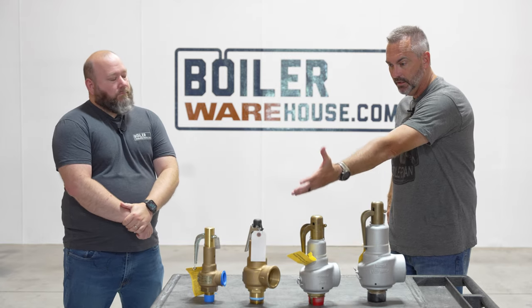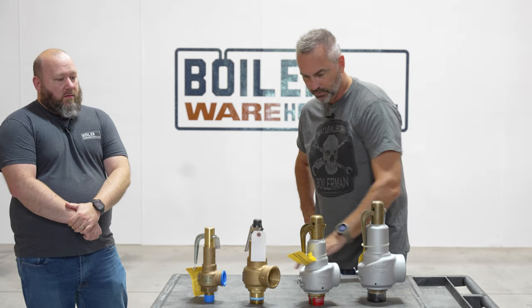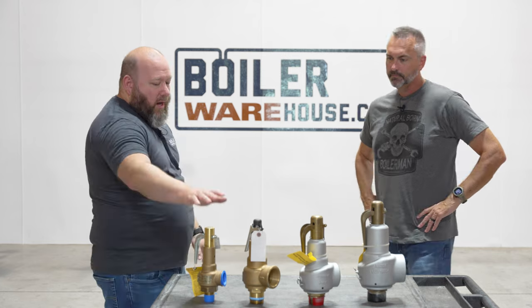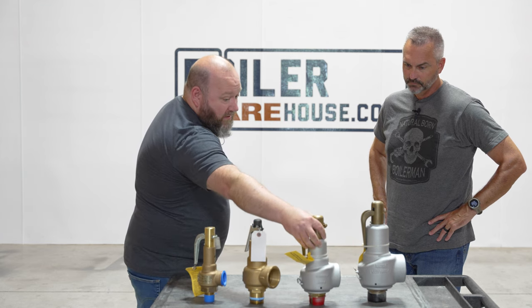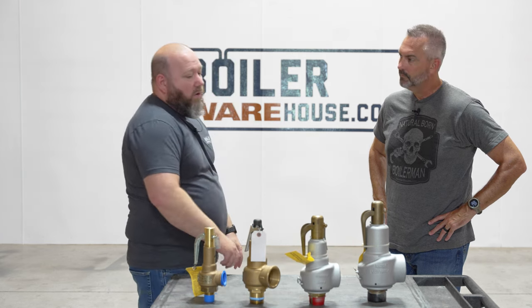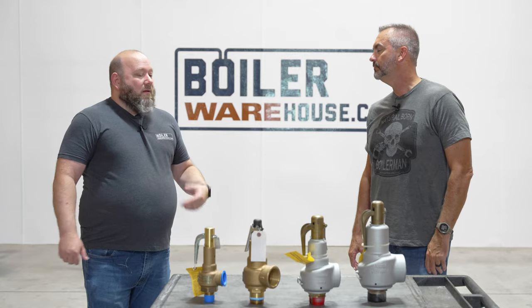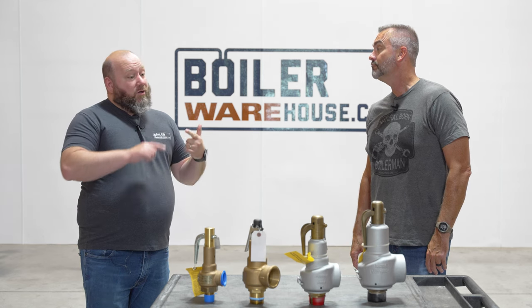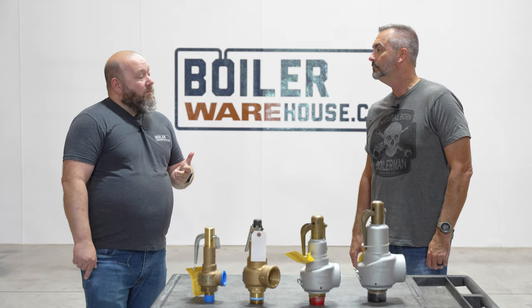There are different types and brands of relief valves. We've got an Apollo, some Consolidated, and a Kunkle here. This is an Apollo bronze and this is a Kunkle bronze — they look very similar. The Consolidated is actually a painted bronze valve as well. There are also steel valves, larger flanged valves, and hot water relief valves that have a temperature probe on them — temperature and pressure valves. There are a lot of different valves and applications. The big thing is knowing what you're putting it on, matching the application to the correct code that applies, and making sure you've got it sized correctly.